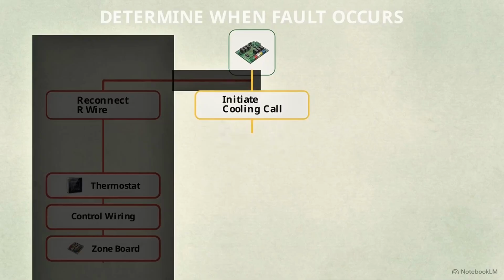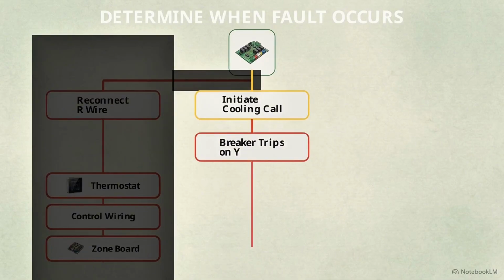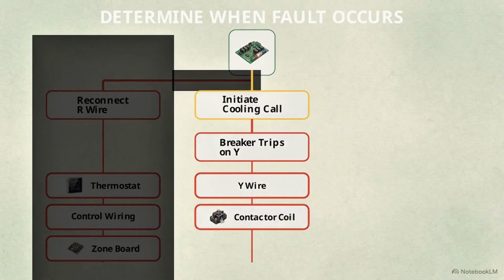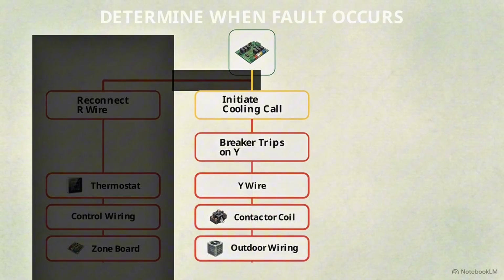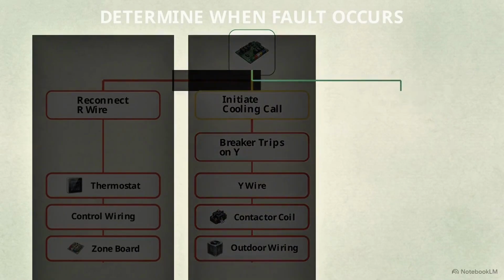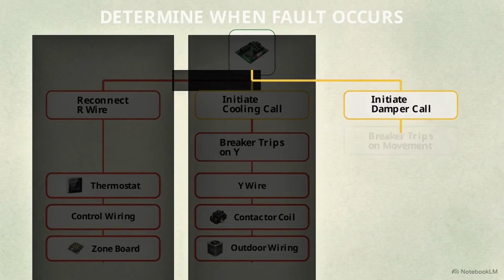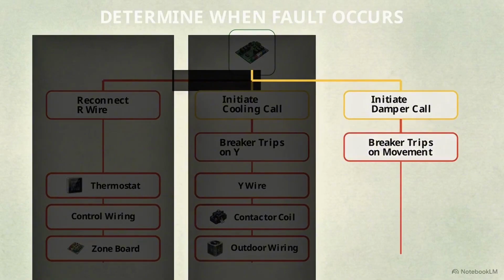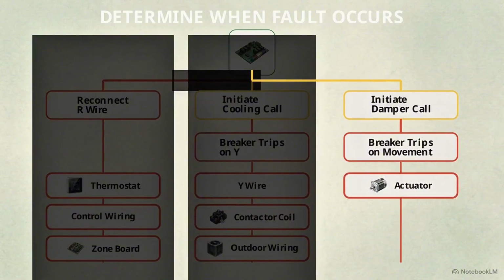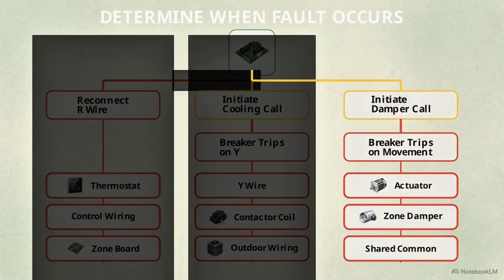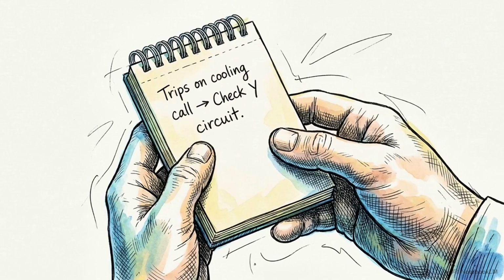Following the cooling path on the flowchart, if the breaker trips when the system calls for cooling, the fault lives in the Y wire, the contactor coil, or the outdoor wiring. Alternatively, if the flowchart logic moves to a damper call and the breaker trips exactly when a zone damper attempts to move, you limit your search to that specific actuator, its wiring, or a shared common. Taking careful note of exactly when the fault occurs tells you exactly which circuit to test next.